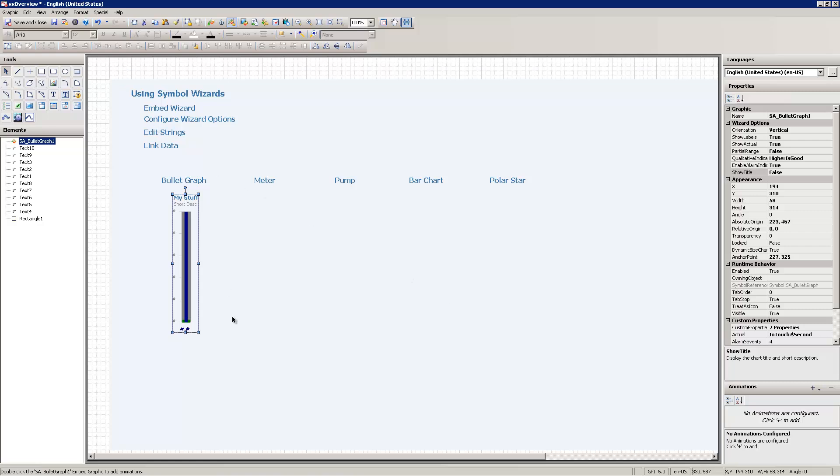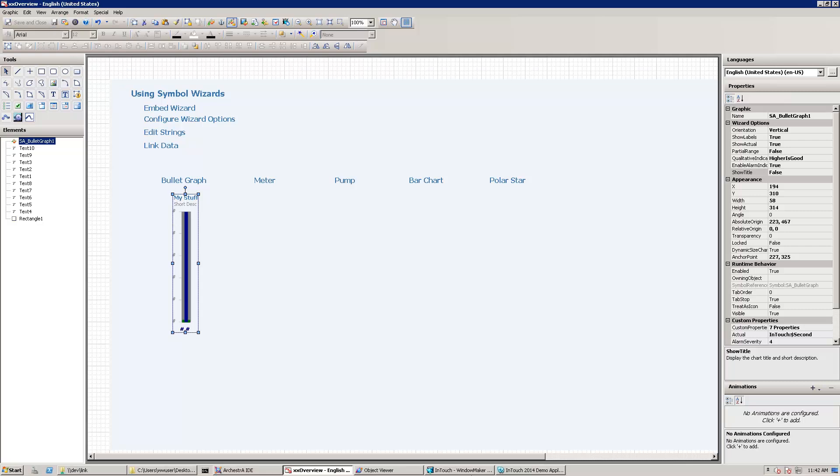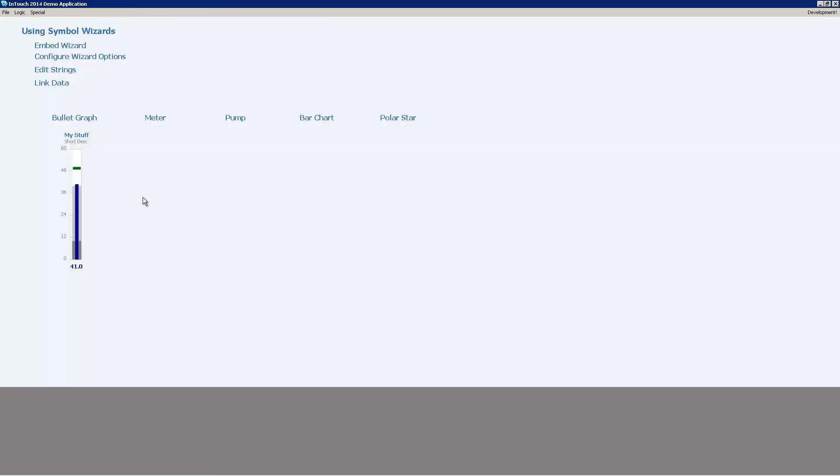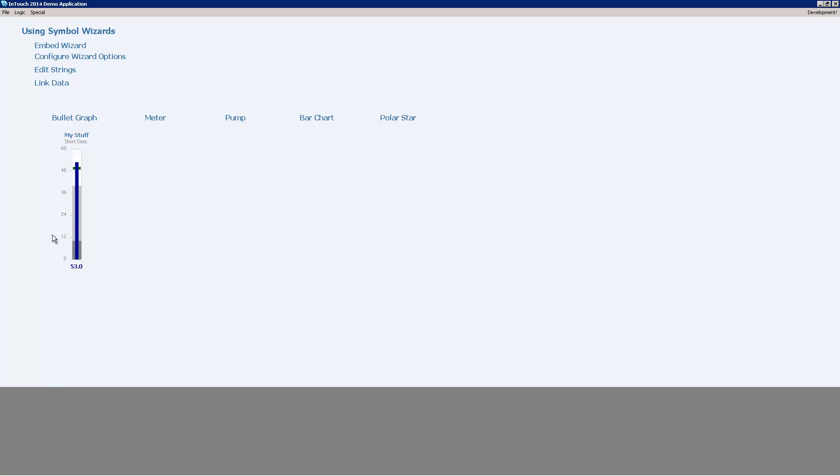Now I've gone through all the steps to create and edit my bar graph symbol wizard on this overview display that I'm creating. So I'm going to go ahead and save the work I've done, and I'm going to go see if it's working. I'm going to pop over into the runtime here, and sure enough, everything looks like it's working fine. So I've got the data coming in, the bar graph is showing. It's showing me the bad indication range, the satisfactory, good range, my target value. All of my value labels have been set appropriately. So I'm good to go.